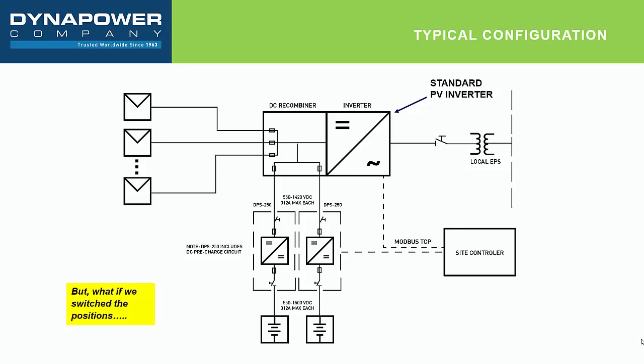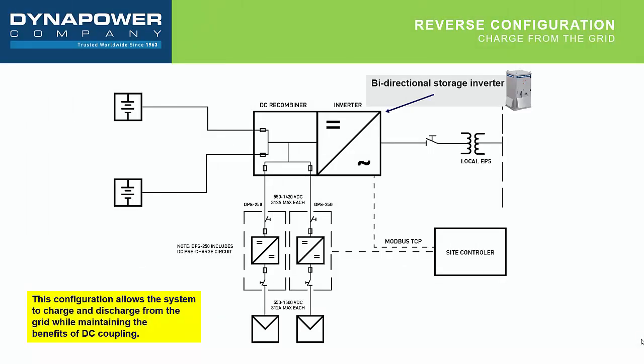Now, we'll show a slightly different configuration here. I talked before about the fact that you cannot charge your batteries from the grid in this new DC coupled configuration. But what if we needed to charge the batteries from the grid for a particular use case, and we're not concerned perhaps about the tax credit? Well, you can actually flip everything around. In essence, here, instead of a storage system tied to a solar array, we essentially have a solar array tied to a storage system, whereby we have a standard bidirectional storage inverter. So now in this configuration, you are able to charge the batteries from the grid, and you are still DC coupled, so you're able to take advantage of all the other advantages of a DC coupled system. So in effect, you can have your cake and eat it too with this, what we'll call a reverse configuration.